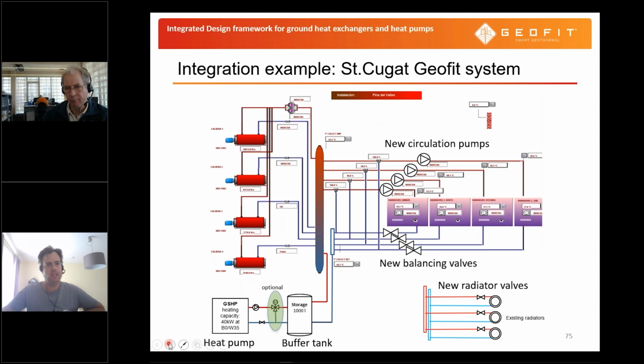the heat pump operation. And in that way, of course, we need new radiator valves because we now have the heat pump operating at lower temperatures. We need new circulation pumps, balancing valves, of course, a storage tank, and here the heat pump. So this is not a very detailed hydraulic layout, and this will be shown next week.